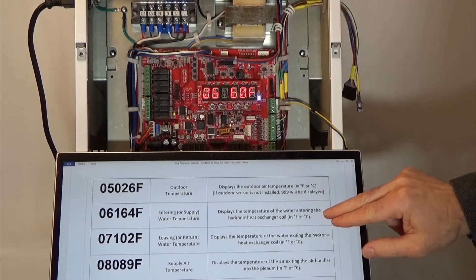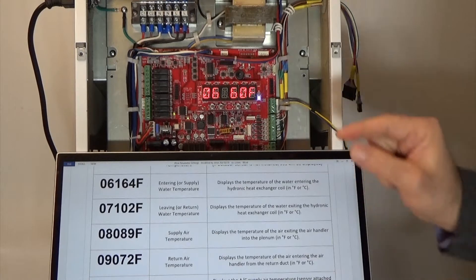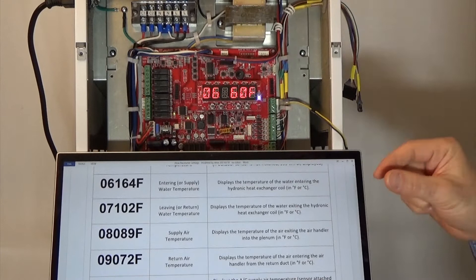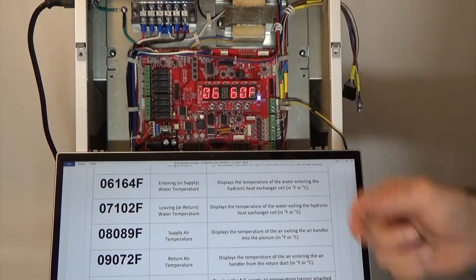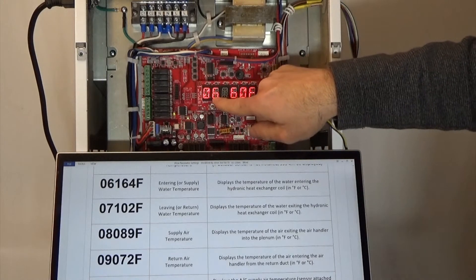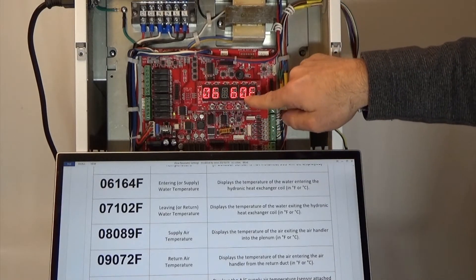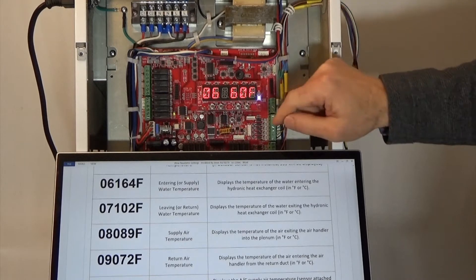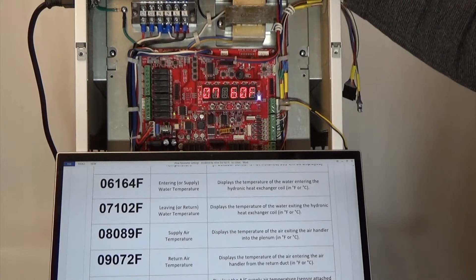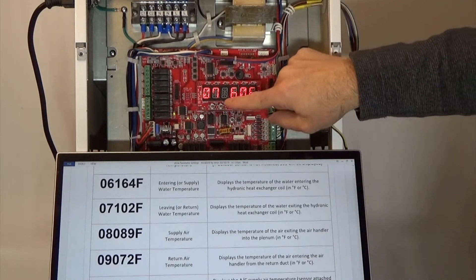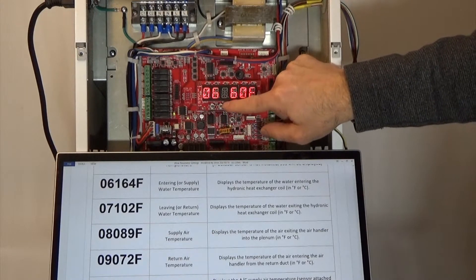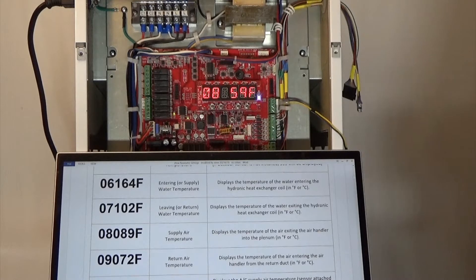Parameter six is the entering water temperature. In parameter three we gave you the delta T — we calculate the delta T across the coil. In parameters six and seven, we give you the actual values we're seeing. Parameter number six tells you the incoming water temperature, and parameter number seven tells you the outgoing water temperature. Because this unit is not on, it makes sense that both six and seven give us the same temperature, since they're seeing the same temperature.